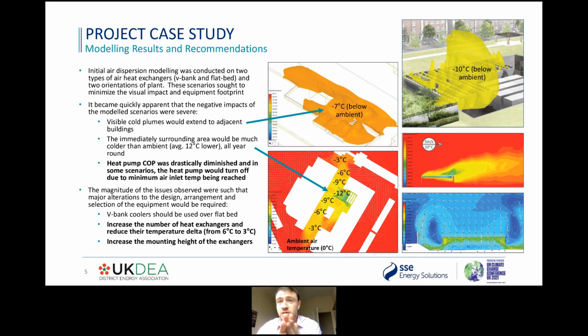We had cold plumes, 7 degrees below ambient, extending far out in the road. You can see that the first picture with the orange splodge is a cold plume across a 50-meter area, and you can see it actually touching that residence building right beside the installation. The surrounding area would be significantly colder than ambient. It was an average of 12 degrees all year round because these heat pumps are operating on a continuous 24/7 basis to provide the base heat load for the scheme. The net effect of that operating continuously was a 12-degree reduction in ambient temperature, which is obviously less than desirable. Maybe nice on a summer's day, but certainly in winter that would be less than comfortable.